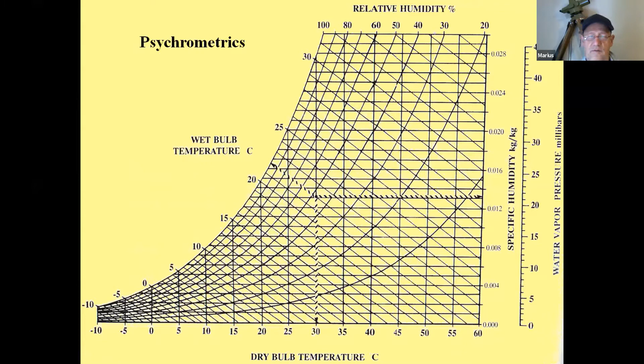And this is what we use the chart for. We measure certain factors, and then we deduce from the chart the quantum of the other factors. Okay, let's just talk about humidity because it's sometimes a bit confusing for people. We tend to talk about humidity, and it's actually relative humidity which is relevant to us, but there's also a humidity called specific or absolute humidity, which is also referred to as the mixing ratio. And that refers to the mass of water vapor per unit mass or per unit volume of air.